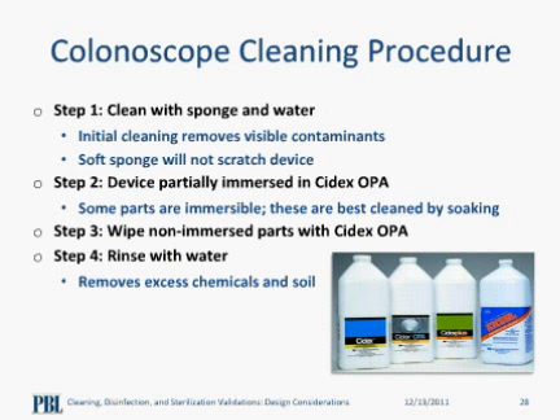All parts that cannot be immersed in fluid were cleaned using the sponge and disinfectant. These are usually the parts that don't come in direct contact with the patient's mucosal surface. All the parts that were immersed in fluid were rinsed thoroughly in clean DI water to remove any residuals from the soil and chemicals used for cleaning.